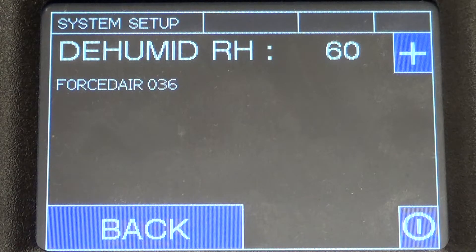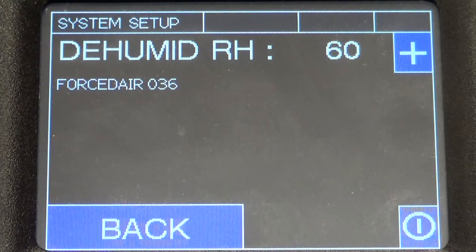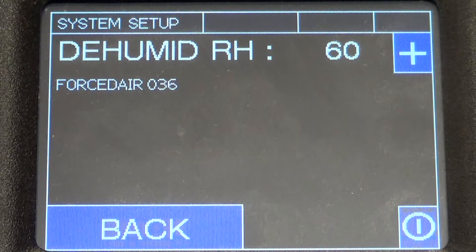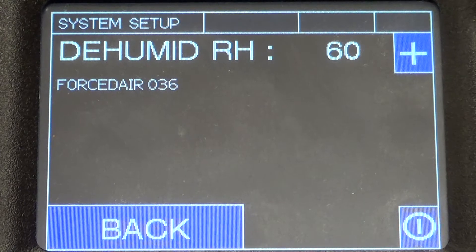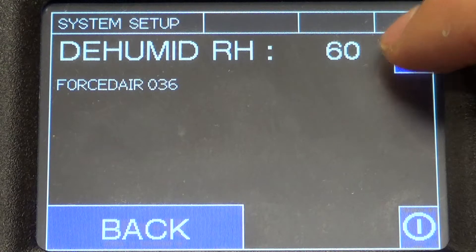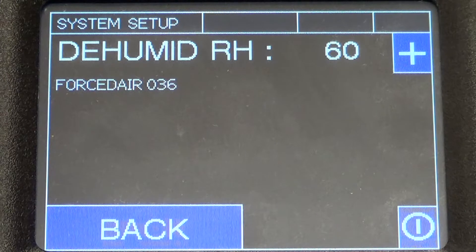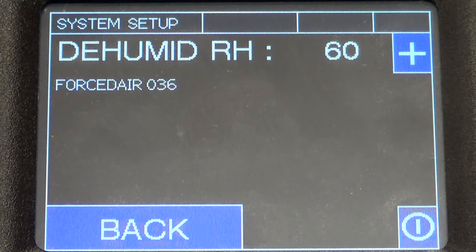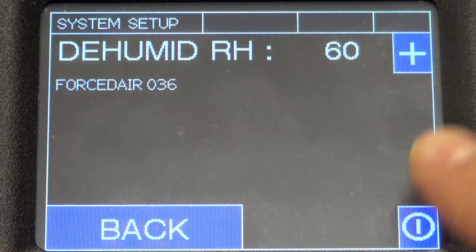For dehumidity control, if you have a thermostat with humidity control, you want to set this number closest to your most common relative humidity set point. The ORB allows you to toggle between 60, 70, 80, and 90. Increasing this number slows the fan down more when there's a dehum call to strip more moisture out of the air. In this example, we'll select 60.